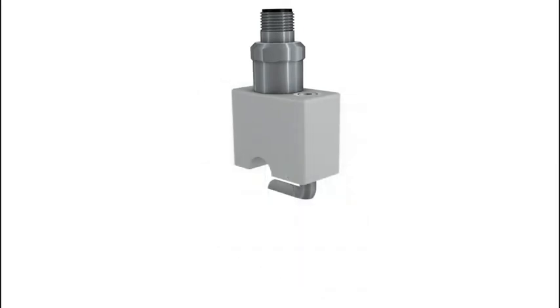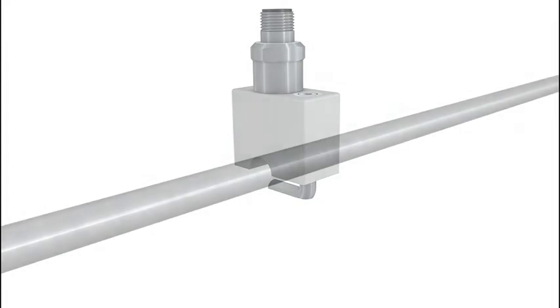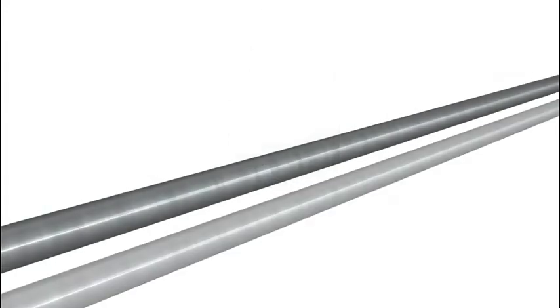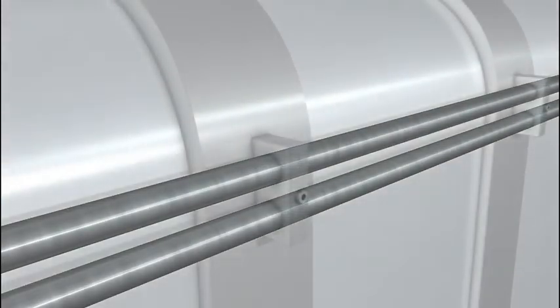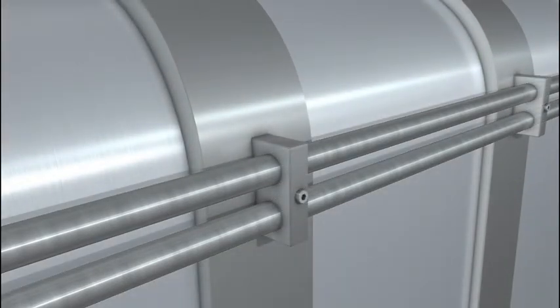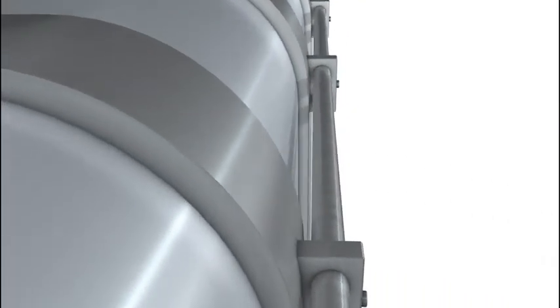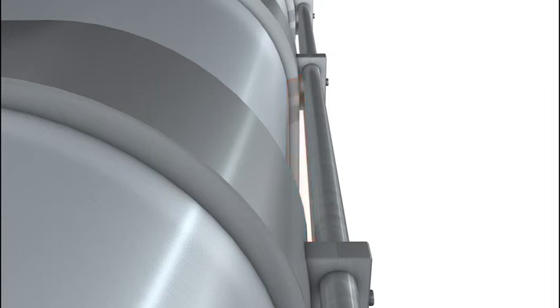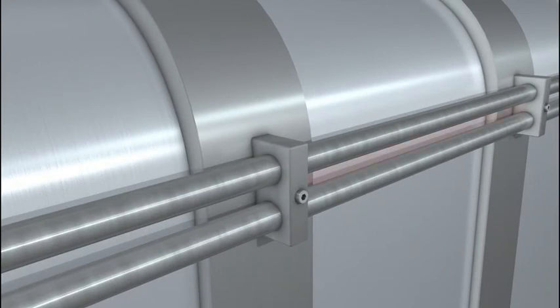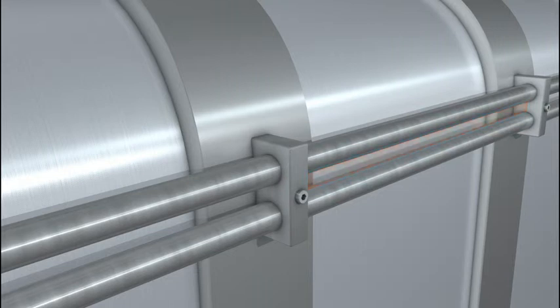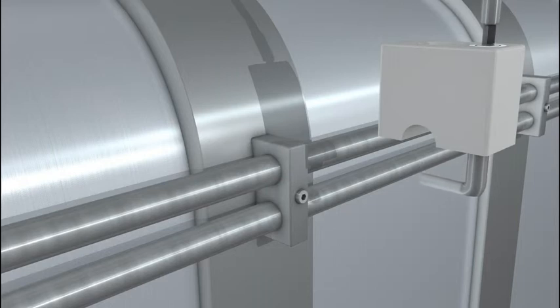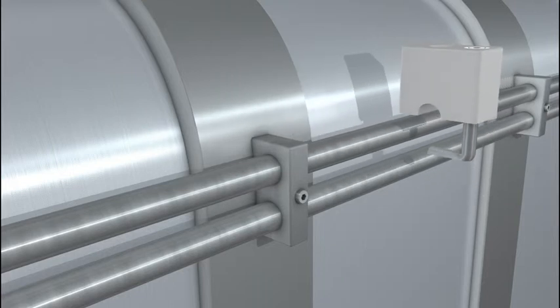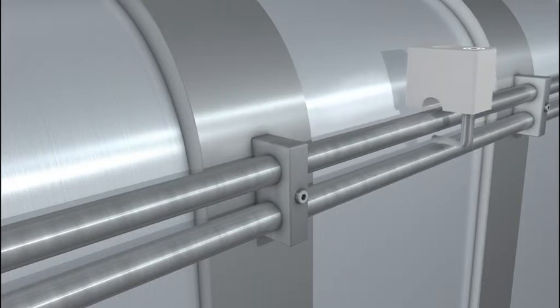A mounting bracket can be used instead of the clamp block to mount devices in tight spaces, for example near walls or close to other pipes. In this example you can see how the device is mounted between two lines using a mounting bracket. In this case the bottom part of the clamp block is replaced by a bracket. The bracket is loosened to allow the block to be fitted to the pipe. The screw is then re-tightened and the sensor is reattached to the block.